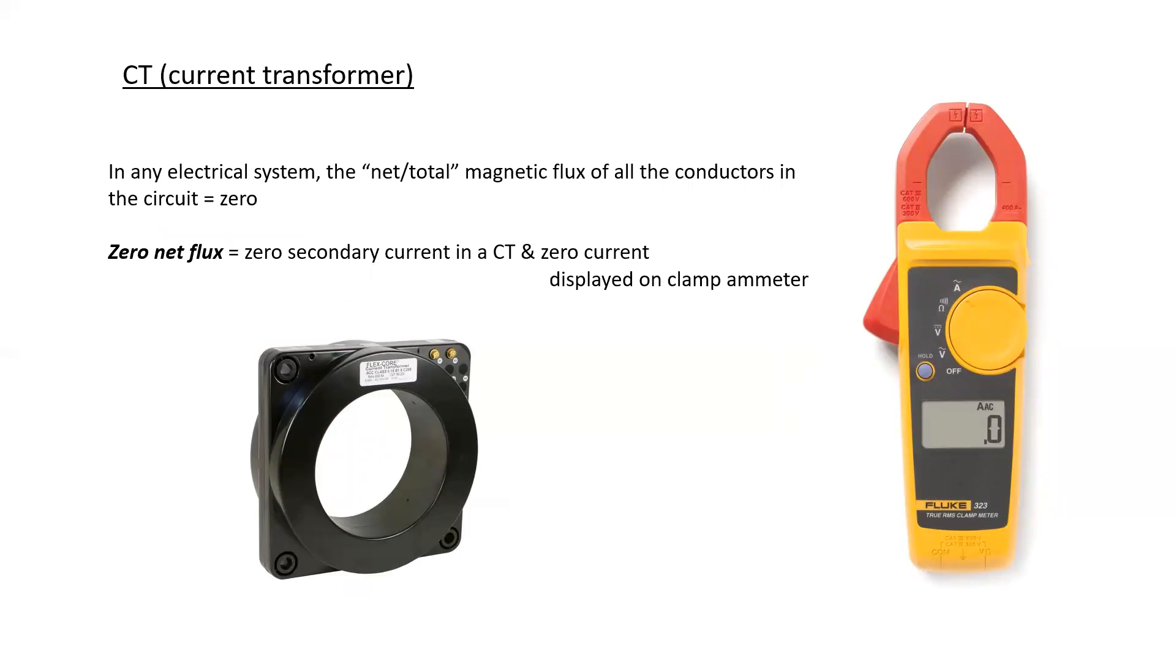For baseline, in any electrical circuit, the net total magnetic flux of all the conductors in the circuit will equal zero. And what this means is that zero net flux will result in zero secondary current in a CT, or zero current displayed on a clamp ammeter.